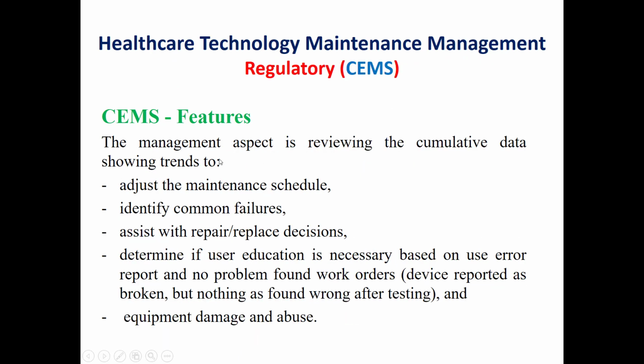So the management aspect is reviewing the cumulative data which will be used to adjust the maintenance schedule. So the gathering of data will be used to perform a lot of tasks to improve the performance of the clinical engineering department or the healthcare technology department. We will take actions, as we said, to adjust the maintenance schedule, to identify common failures, and to find the action which will be suitable to prevent the occurrence of such incidents or failures.